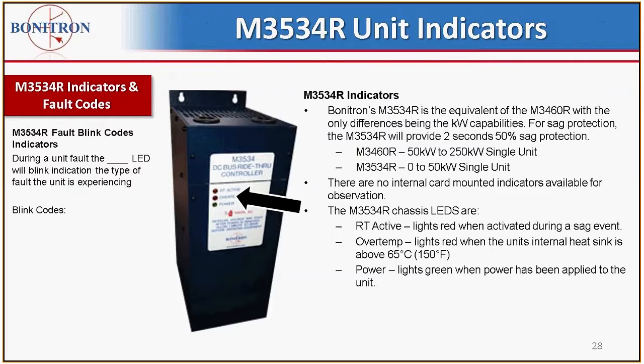But the 3534R chassis LEDs will allow you to have some idea of what the status of the unit is. You have a ride-through active light that should light during a sag event when the ride-through is actually riding through and providing DC bus voltage. Overtemp light lights when the unit's internal heat sink is above 65 degrees centigrade, 150 degrees Fahrenheit. And when you initially power the unit, you're going to see the green light, which is the power light. That should turn on right off the bat when everything is energized, regardless of ride-through event or not.